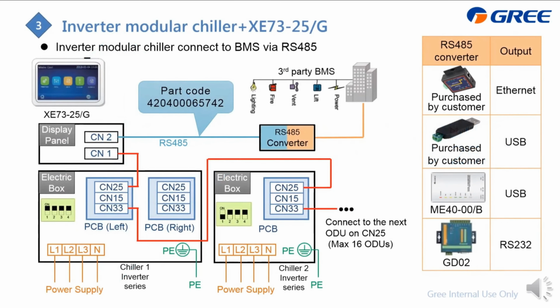This slide displays how to do the modularization of the chillers, and then from the Y controller to the BMS system. The modularization is similar to previous: you can see here are 2 chillers, and just from the CN25 then to the first CN33, and also from this CN25 to the Y controller. If you would like to connect more than 3 chillers, then also from here the CN33 to the next CN25 is okay. And also don't forget to change the switch to identify your different chillers.